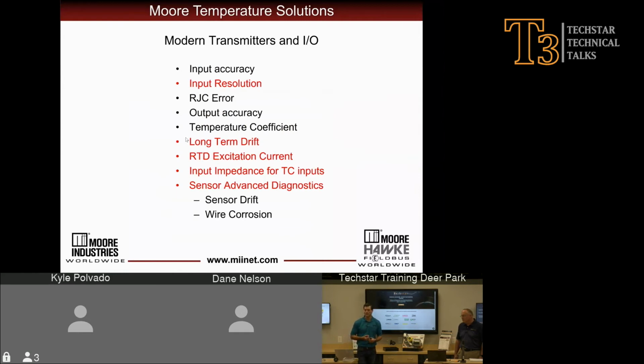Long-term drift, how repeatable is that temperature transmitter over time? So this results in fewer calibrations with a longer drift accuracy temperature transmitter. The RTD excitation current. So we want to make sure that that RTD excitation current is as low as possible so that we don't accidentally heat our RTD element with the constant current we're passing through it.